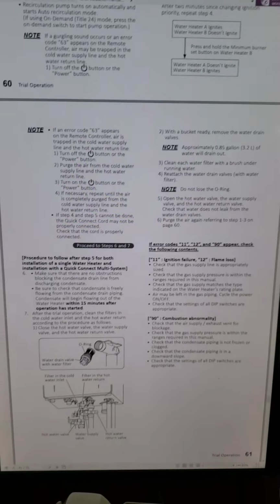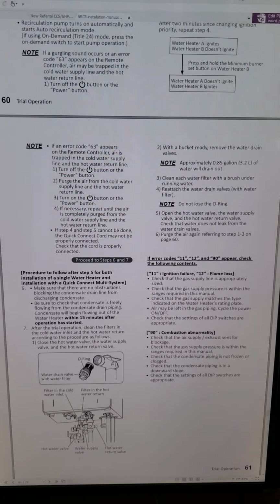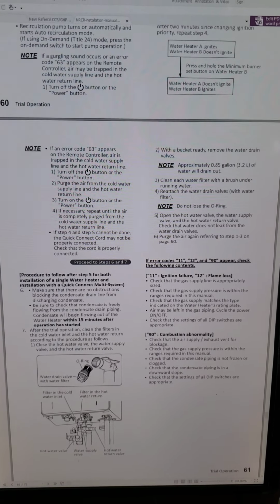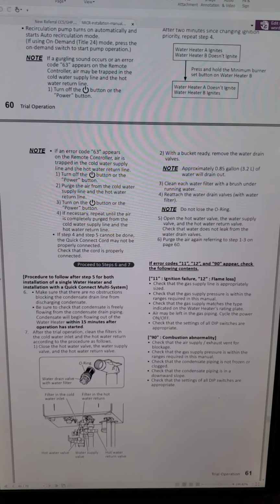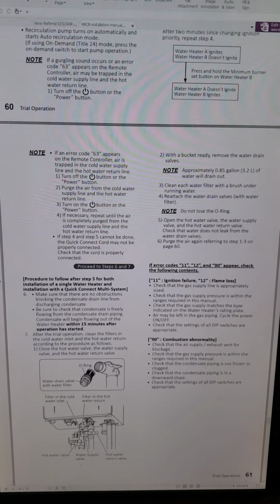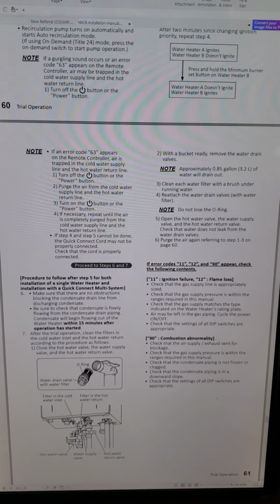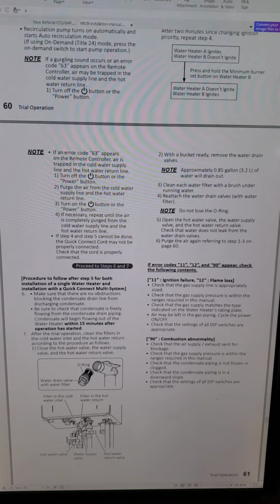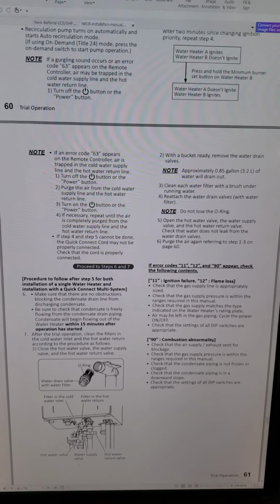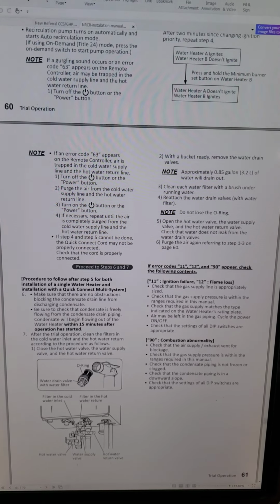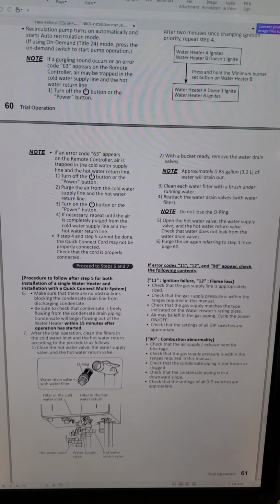The point I'm trying to make is that Noritz should have made a special video or changed the instructions to indicate that error code 63 could be caused by the motherboard, instead of letting people hunt for the reason. If the plumber is not familiar with this particular water heater, you won't be able to figure out what the problem is. They have to call customer service and do detailed diagnosis, which a non-plumber or non-installer may not be able to perform themselves.